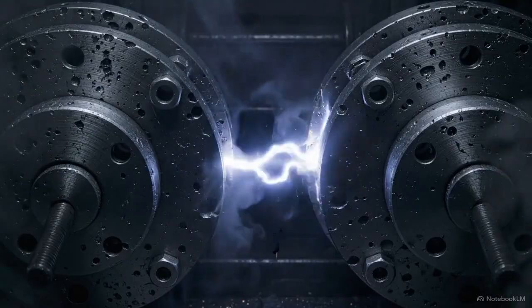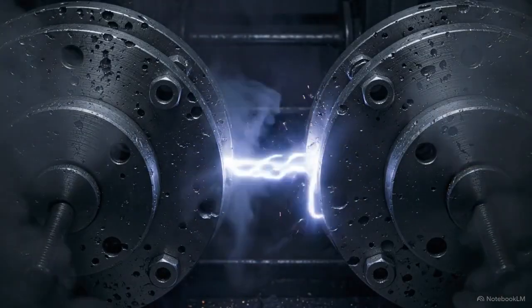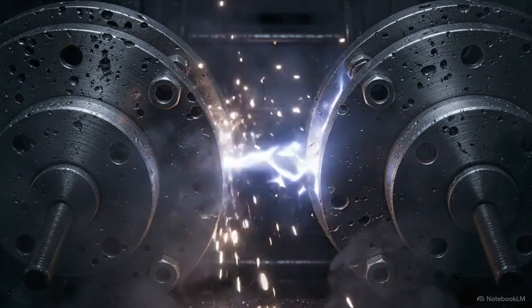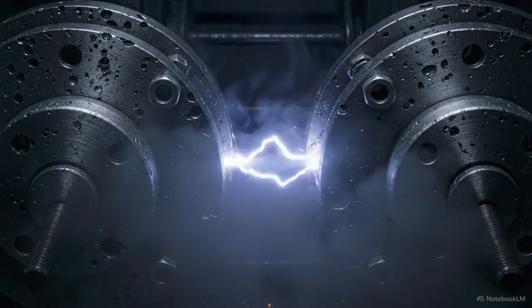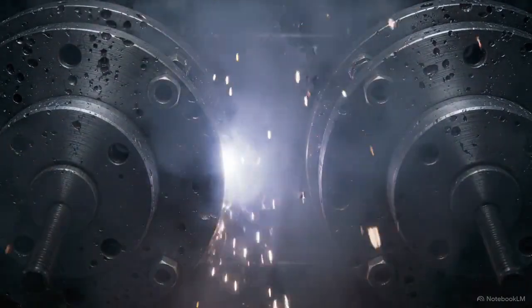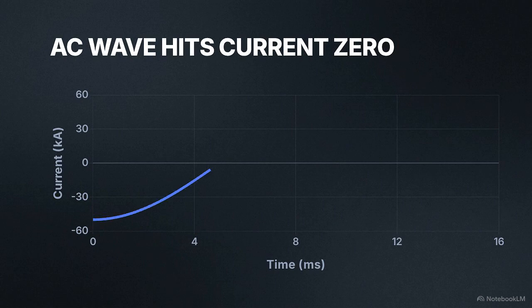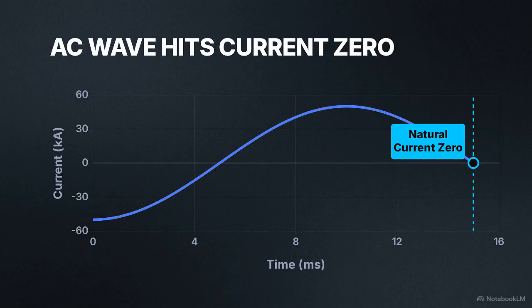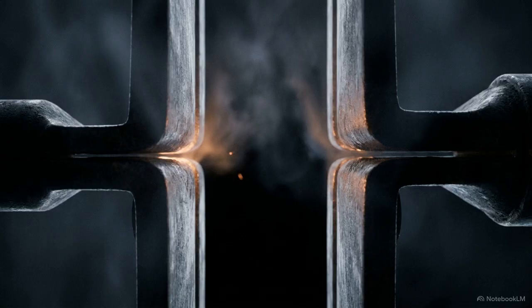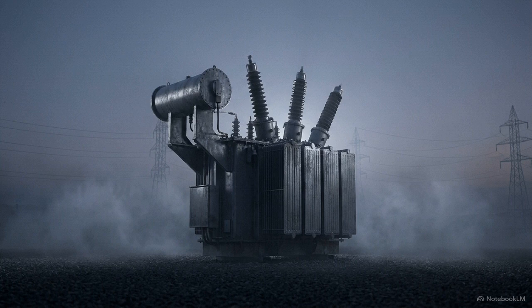The electrical pressure superheats the surrounding gas, creating a blinding plasma arc that allows thousands of amps to keep flowing straight across the physical gap. Because alternating current naturally cycles in a wave, there is a fleeting moment when that current waveform drops to exactly zero. At this precise instant, the arc starves and extinguishes. The current is dead, and the physical connection is broken.